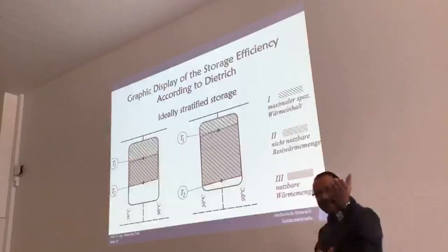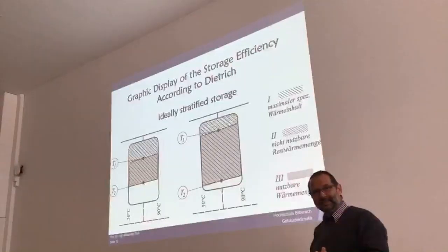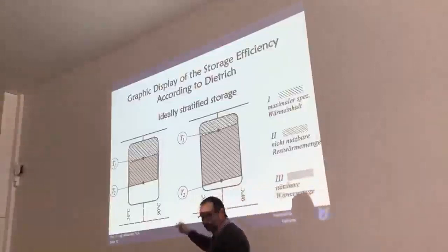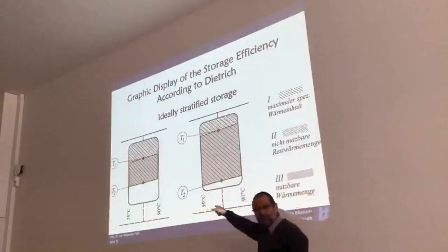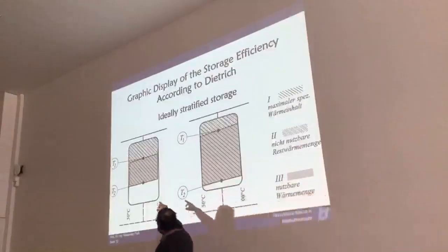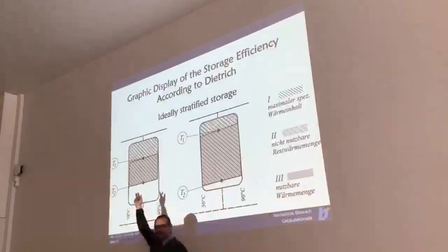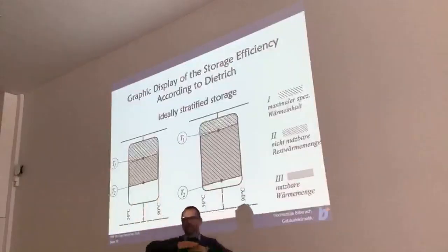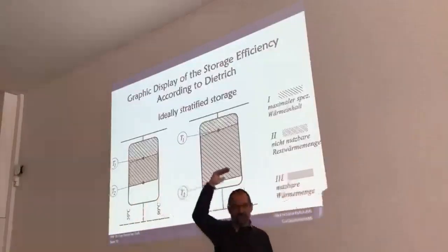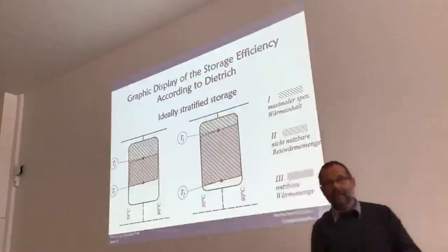And now your question is right. How many you need? Two of them. And where are you going to locate them? Up and down. Yes, and I think you could do it much better than it is shown here. The lower sensor should be as low as possible, and the upper sensor should be as far at the top as possible, because then you get a large area you exceed.